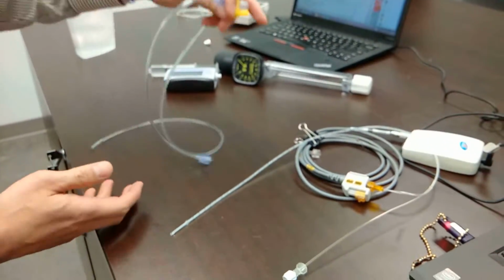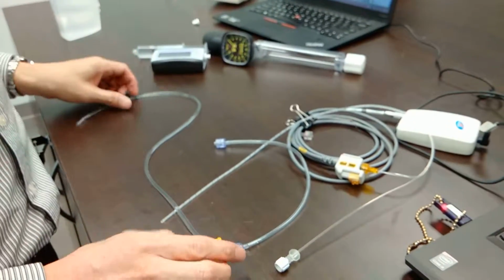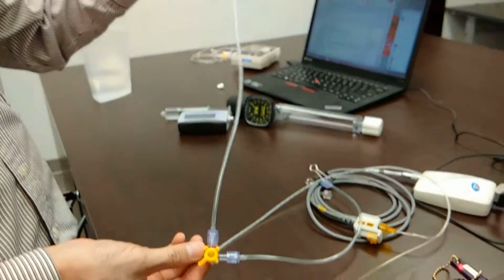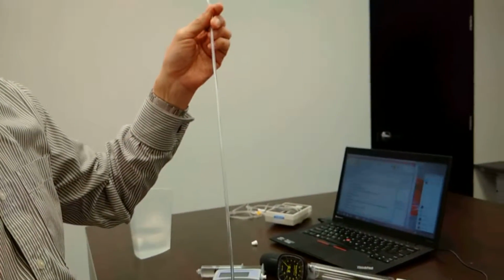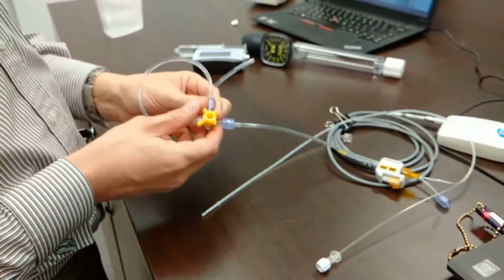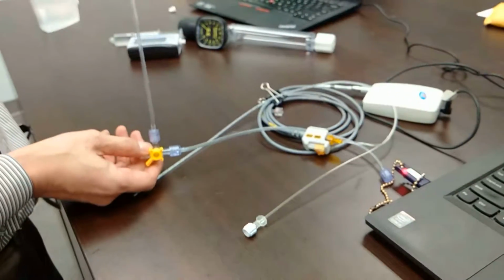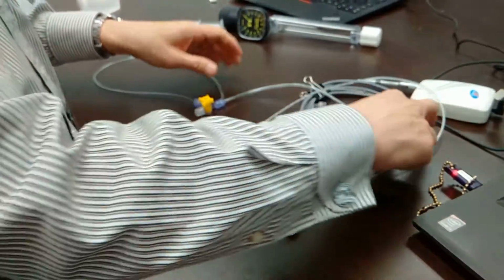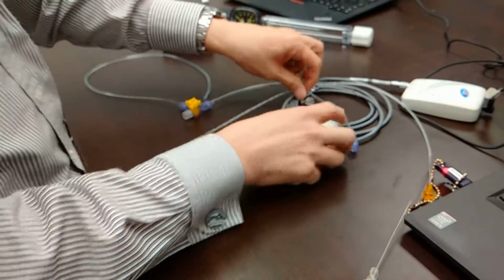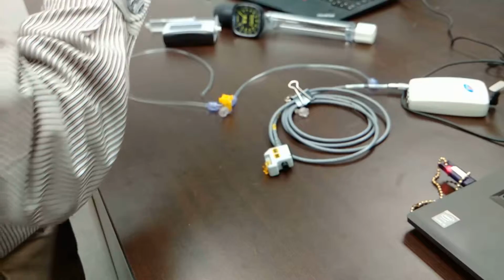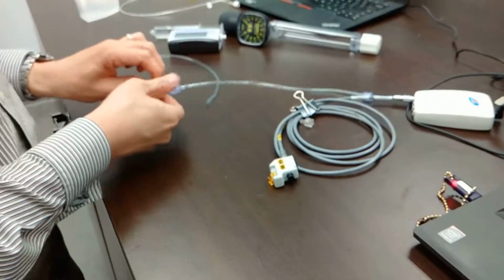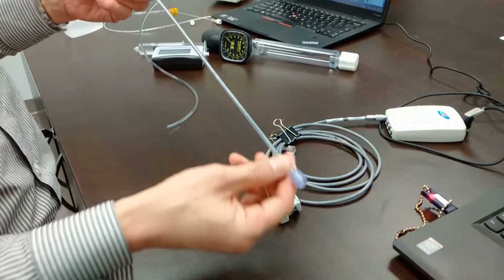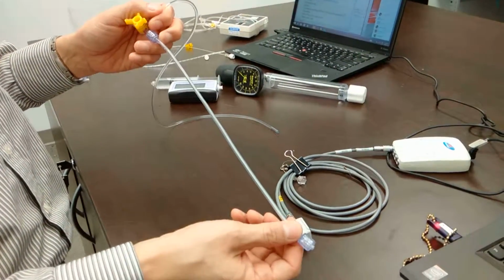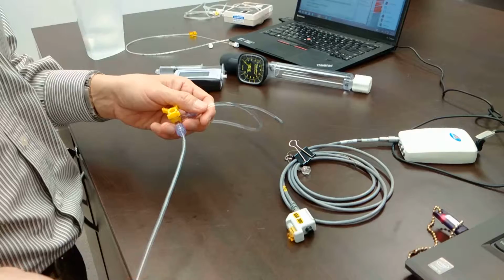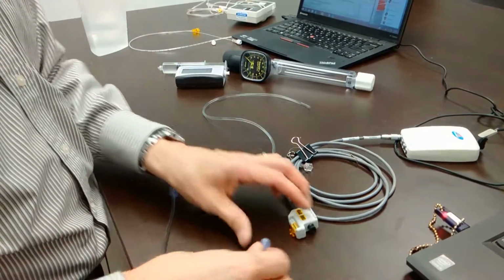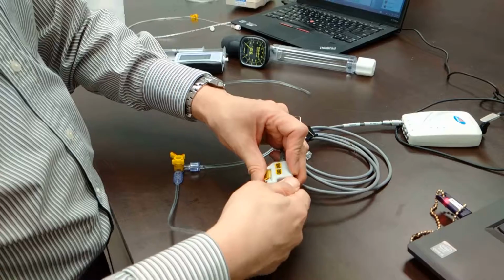So there is actually a water calibration method that we can use using tubing like this. And we know the length of this tubing is exactly 60 centimeters. So what we can do is we can put fluid in here to 60 centimeters and attach it to a TDOC. Now, the air trap tube is designed to work with air and water. This section here is a long air section, because the transducer is not supposed to be exposed to water. Basically, you make the connection here.